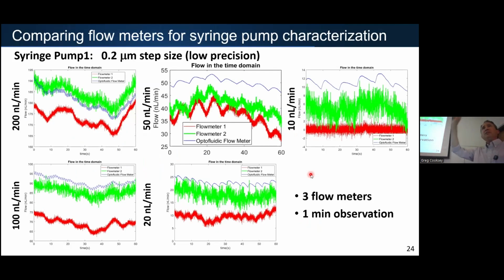If you've seen these, a lot of times these are standard undergraduate and graduate syringe pumps. With the optofluidic flow meter, we can see every single click of the motor on those syringe pumps, and we can look at the inaccuracy based on the setting of other commercial flow rates. Here we're setting it to 20 nanoliters per minute, and it's measuring a little high, so the syringe pump in this case may be a little inaccurate.